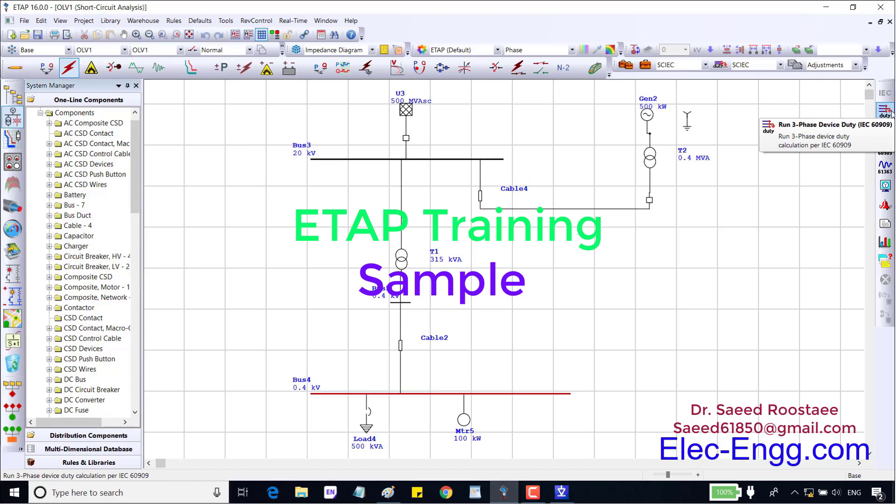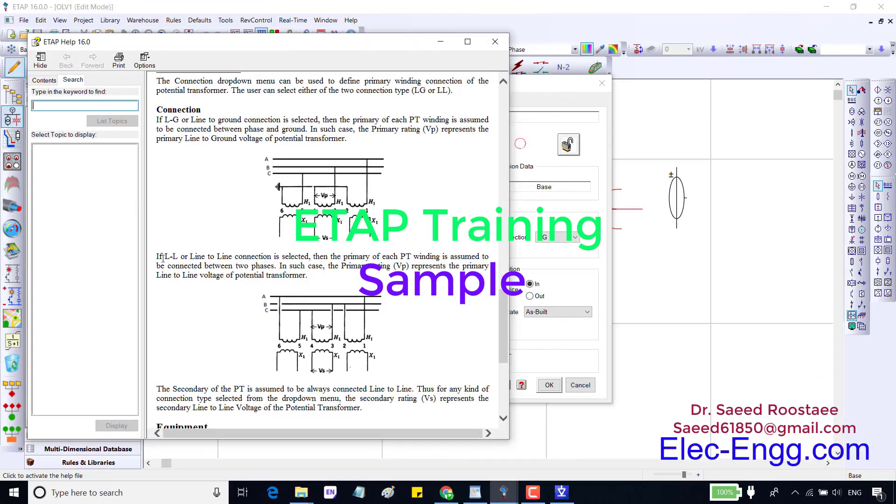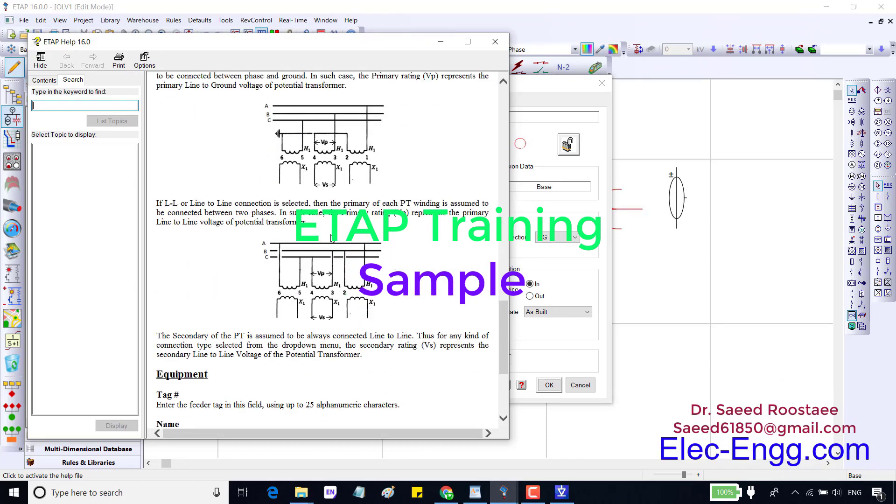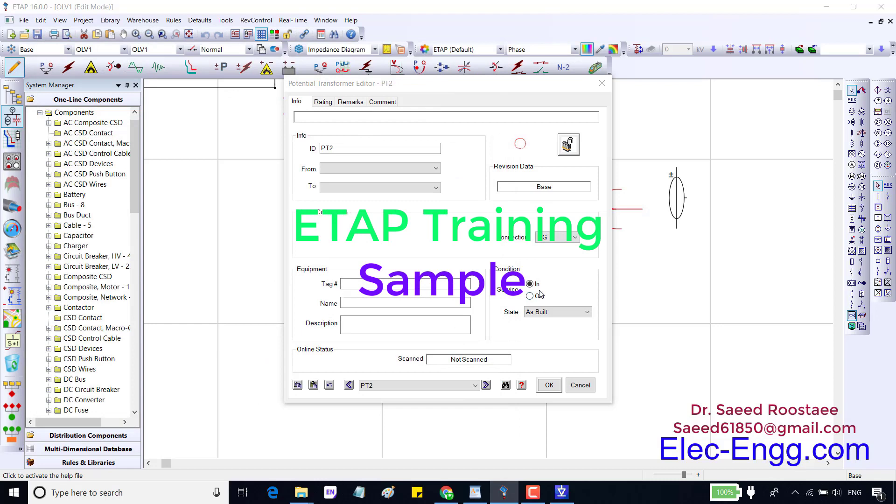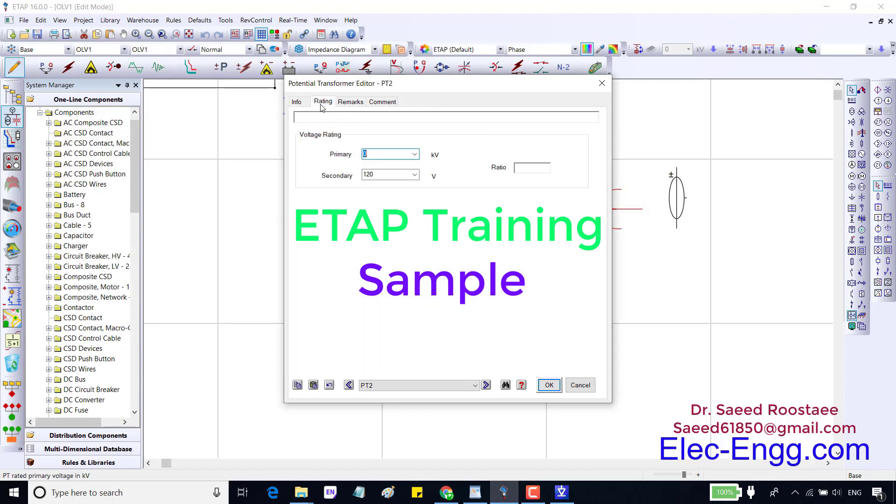In the IEC standard this button calculates the short circuit current based on IEC 60909. We use this method and this connection is LL or phase to phase. Most of the time this connection is phase to ground, but you have to check with your diagram of your project and check this connection type.